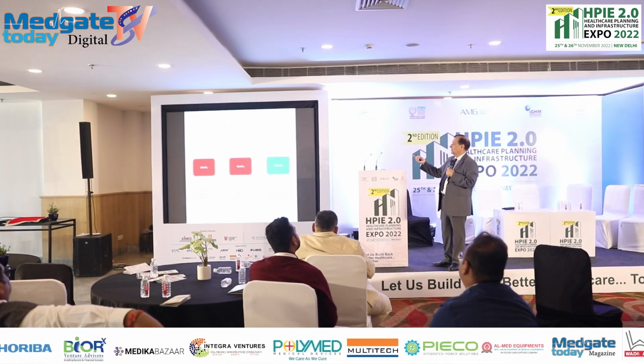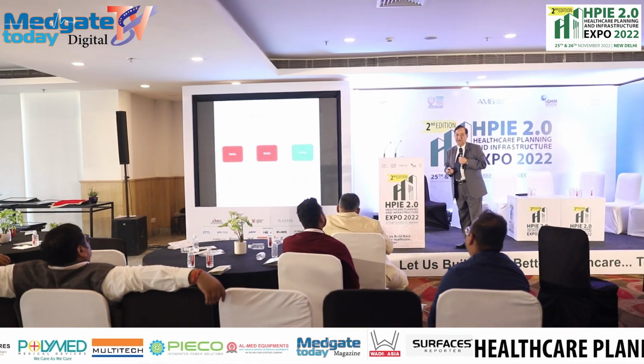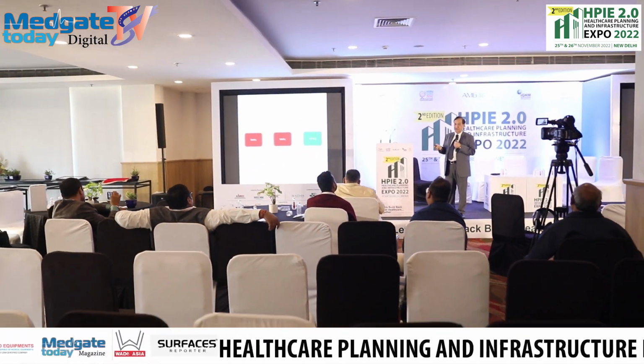This is what people are not tempted to use, but they don't know the other factor, that is, the advantages of using these filters. Industries are using them, all pharmaceutical industries and other applications are using these filters, but the hospital industry just sees the capital cost, and nobody is recommending them. If we can replace these bag filters with these filters, the length of the AHU is reduced by 10 inches and you get 10 inches more space, and the efficiency is better, and you don't need cleaning.